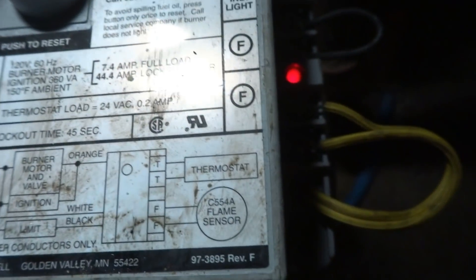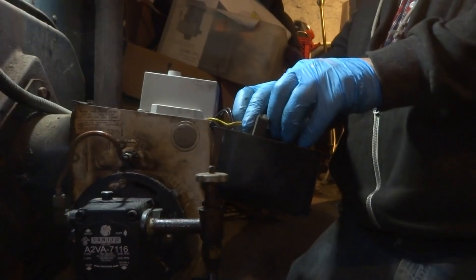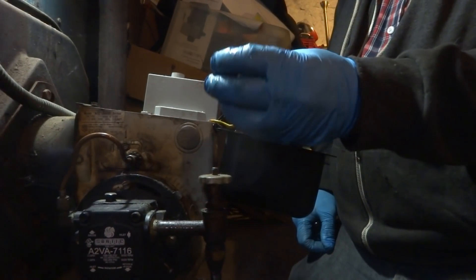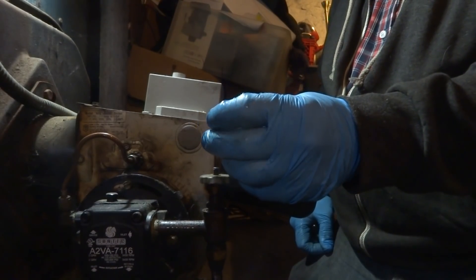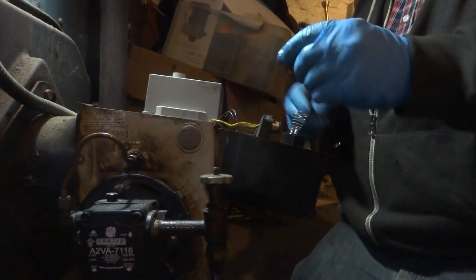She just tripped out. Yeah, it happened when I was right there. There we go. What we're going to do is change the cad cell and this control box — change out the cad cell. I'm going to do the cad cell and this protector relay, change it out.